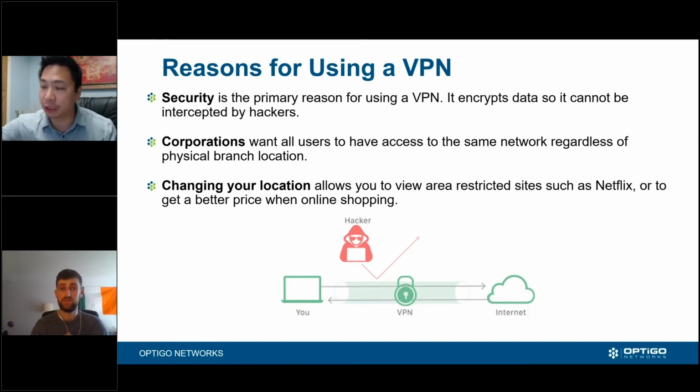In our case, security and the access of two physical places would likely be your reason for doing this, and that's what I was mentioning earlier. If you're looking to use VPN to create one flat BACnet system, you have to be careful which protocol you use, because BACnet leverages layer 2, especially for broadcast, Who-Is, I-Am, unconfirmed COV, and so on. If you don't choose the right VPN, it will break that communication, although typically either a gateway or a BBMD would help in that case.